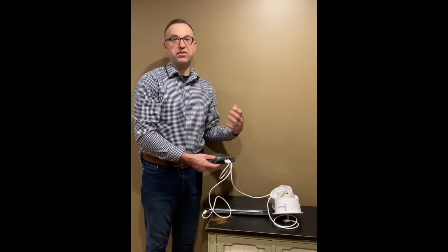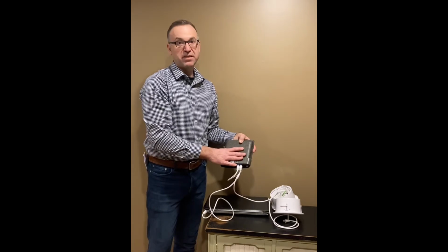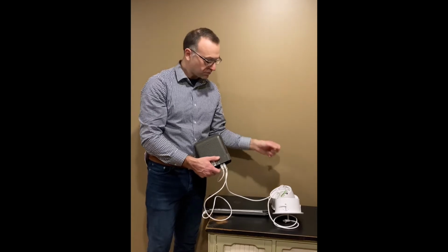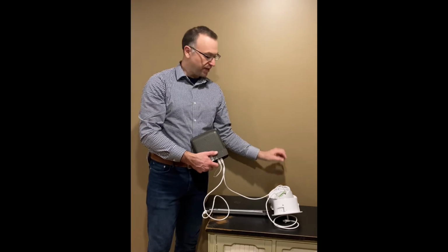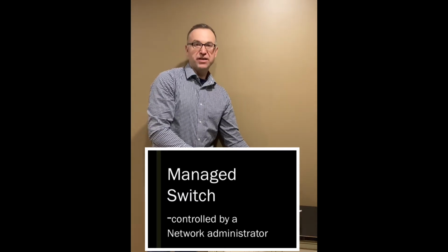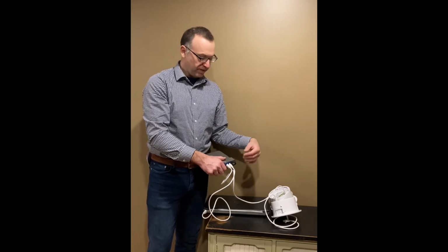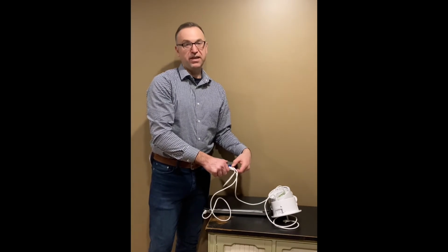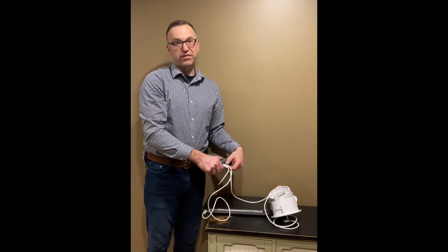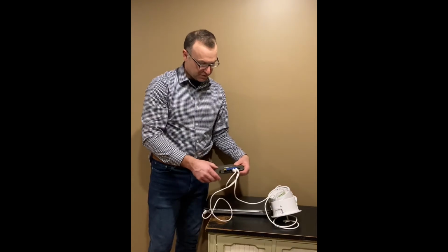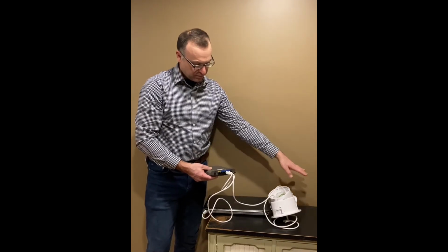But in commercial buildings, large commercial projects, we have a network team that's going to keep track of what's allowed on that network. One way they do it is by MAC address. They can say, I'm only going to allow devices whose MAC address I know on my network. So when something plugs in, they know that MAC address because you've met with them ahead of time. They know that device, they know it's allowed on their network, and it is approved. If it's a device that you simply plug in that's not approved for the network, generally it's going to put that device into a quarantine setting. So that's the simple structure in how we plug in.